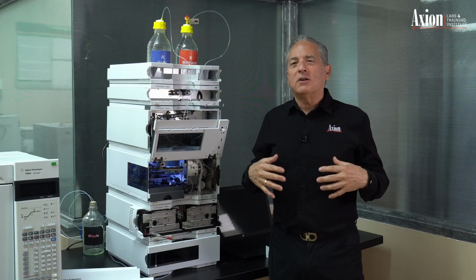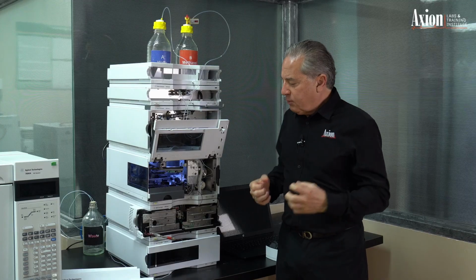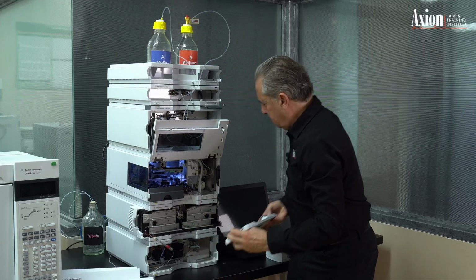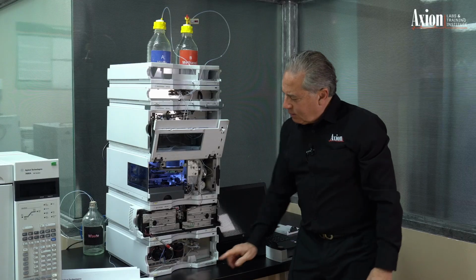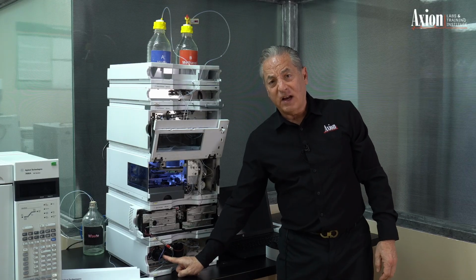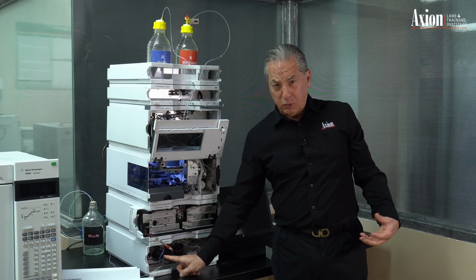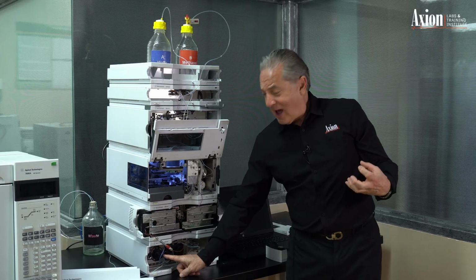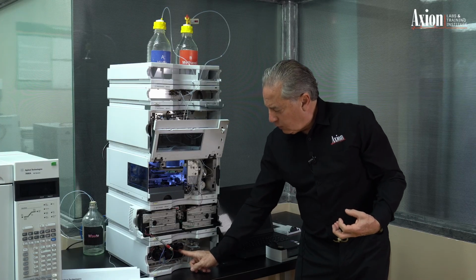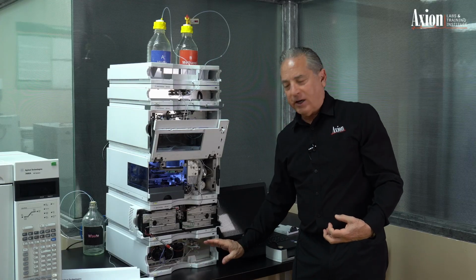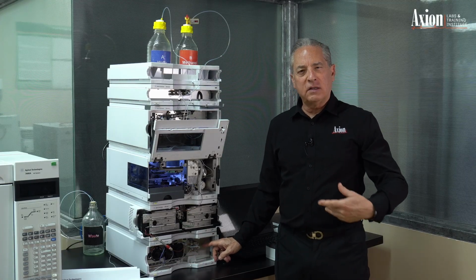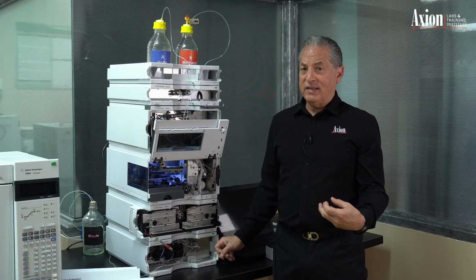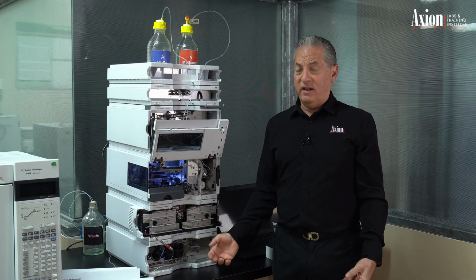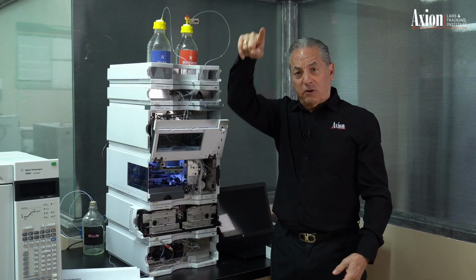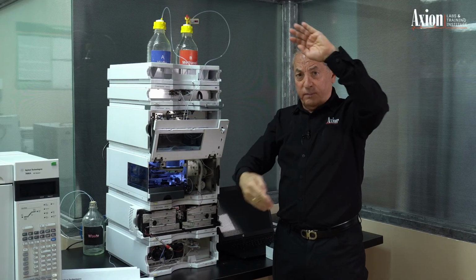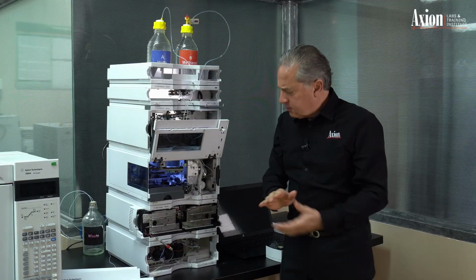So all these UV detectors basically work the same way. We have a really bright light. So if I open up this, we've got a really bright light bulb on the left side of the detector. This is a deuterium lamp. It's filled with deuterium gas. So really high intensity light is coming off of here. It goes through a flow cell, and on the other side, I have a detector. So this detector is going to count the number of photons that go through. So if a sample, an analyte, is flowing through the detector, if it absorbs UV light, the number of photons is going to drop. Since we measure absorbance, we flip that upside down and we see our peaks.